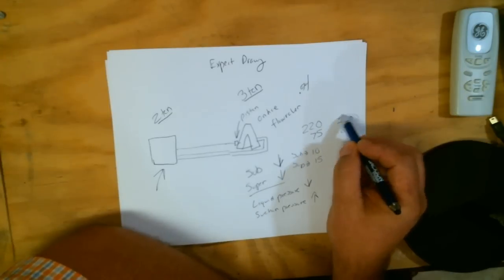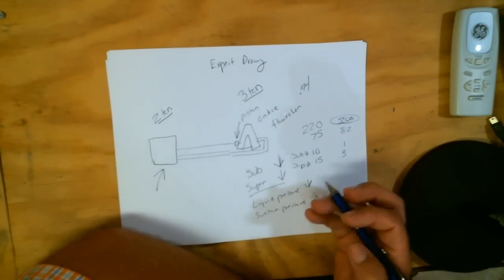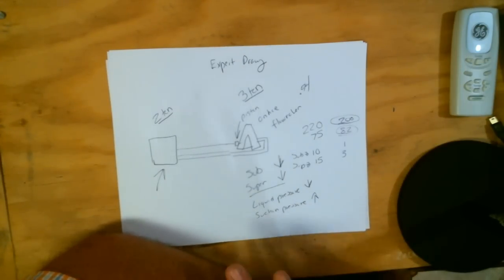So what's the deal? It has symptoms of an undercharge and an overcharge. And then you look at the pressures up here and it's the same thing. Your liquid pressure is too low, it should be higher, so you're thinking maybe I need to add charge. And you look at your back pressure or suction pressure and it's too high, which would indicate you have to take away charge. But think about this: it's not always about the charge, sometimes it's about the type of metering device.